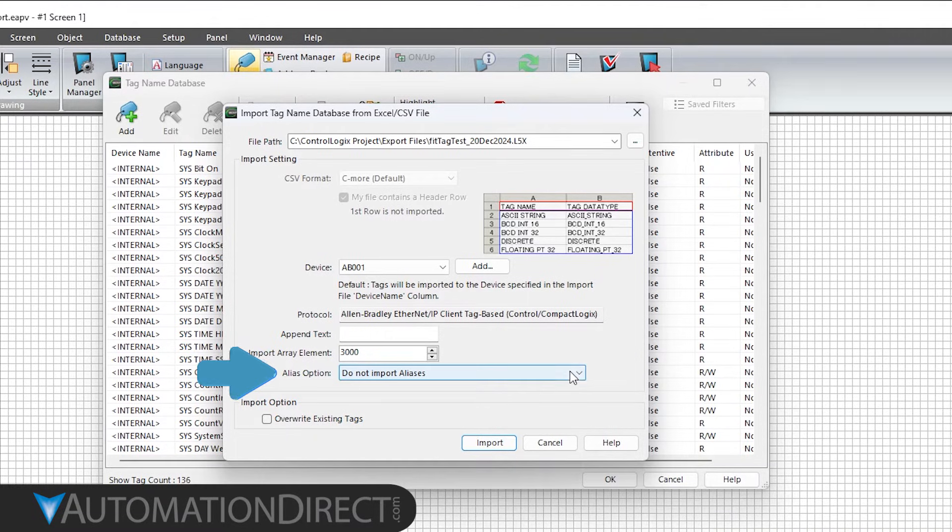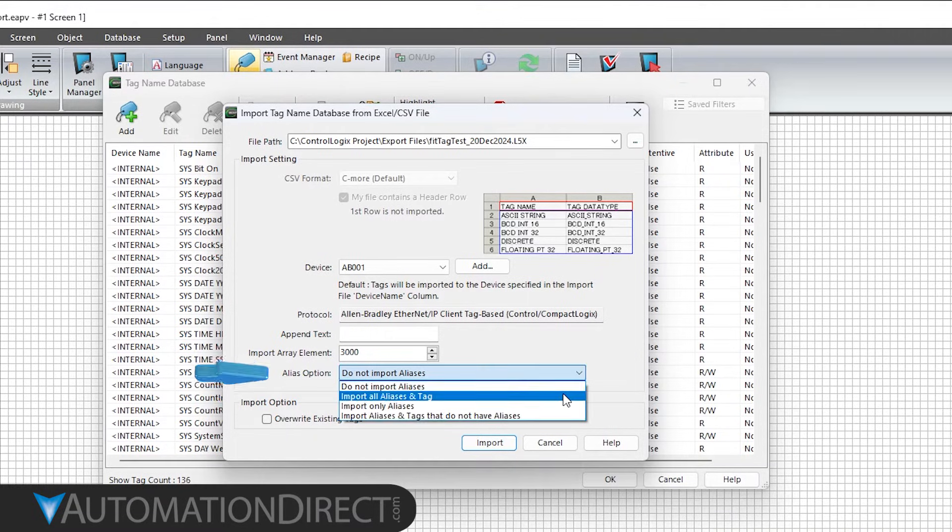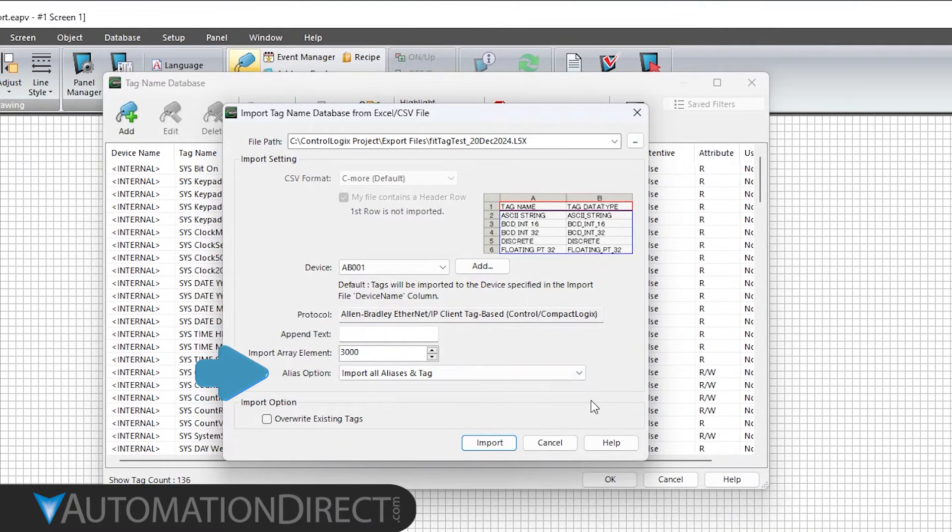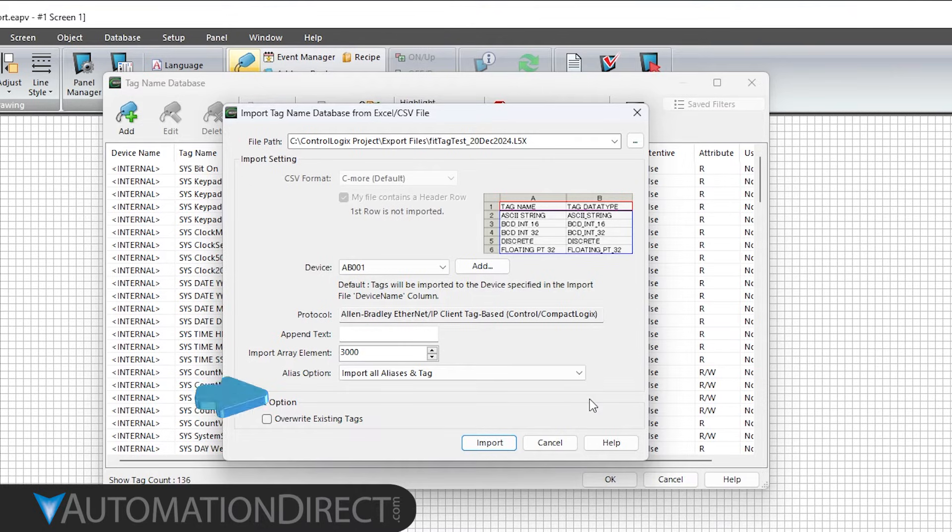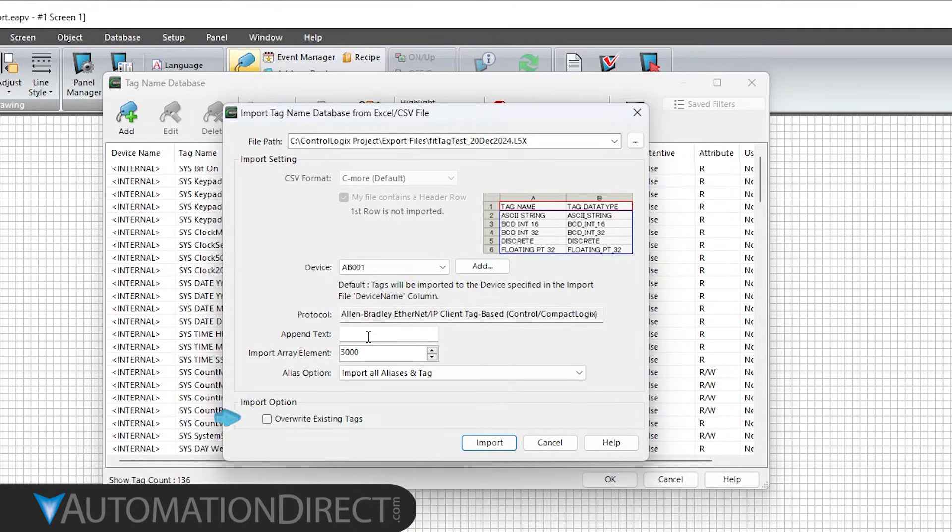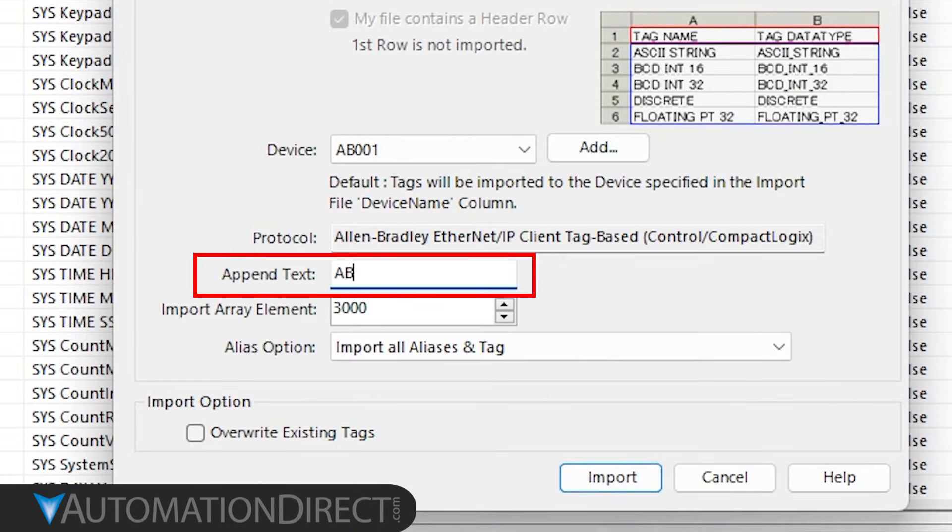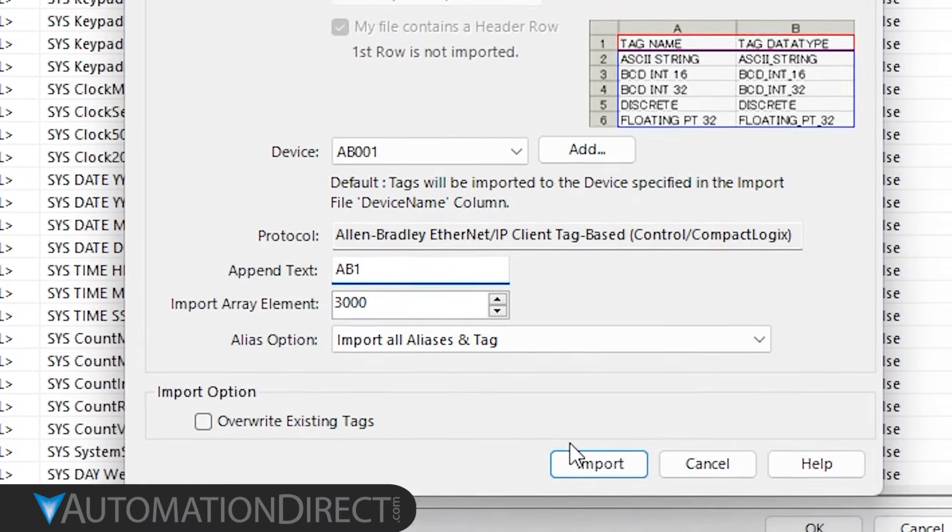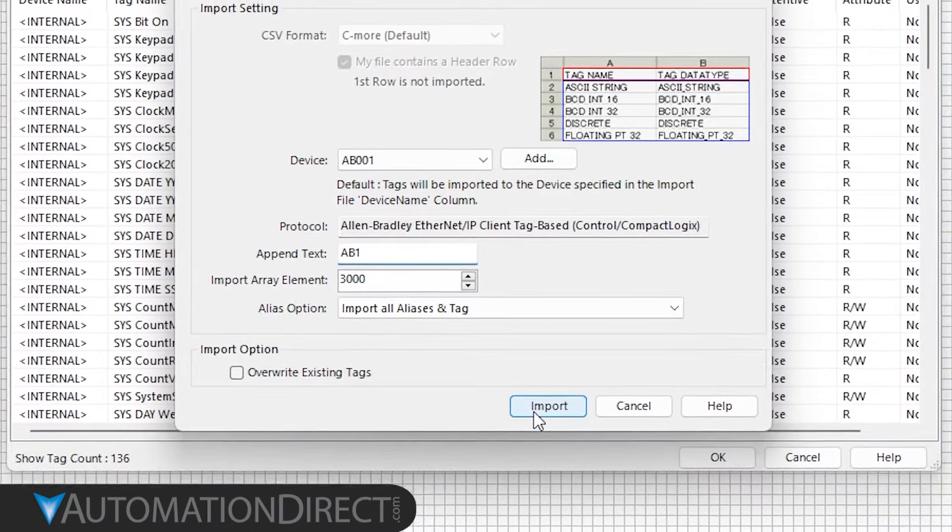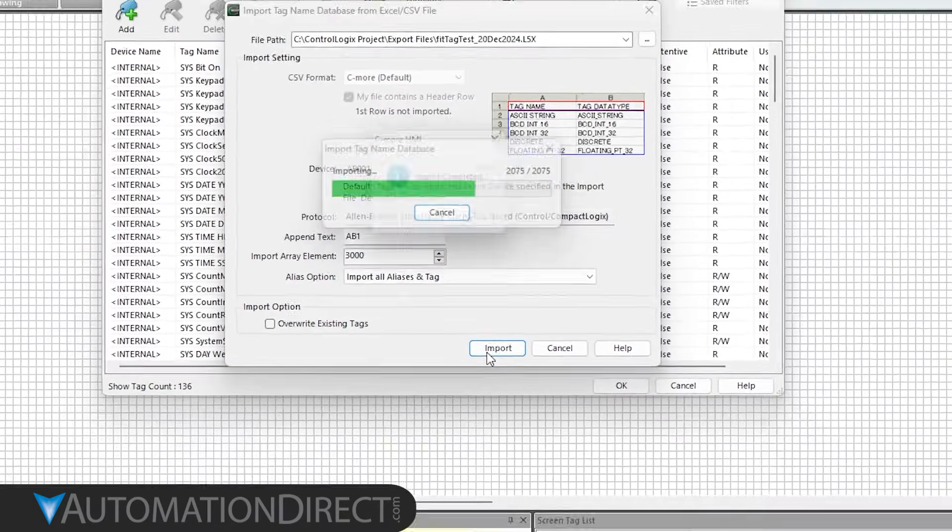If your project uses aliases, select how you want the project to handle that, and checking here will allow you to overwrite duplicate tags. If you're connected to multiple PLCs, it's recommended to add a suffix to the tag names to avoid cross-duplication. Click Import, then OK.